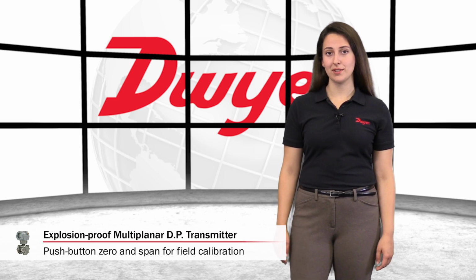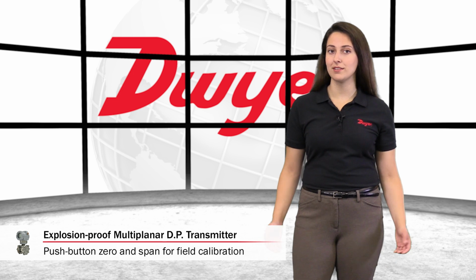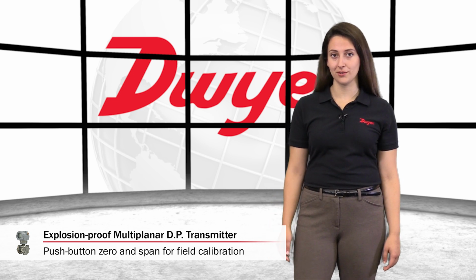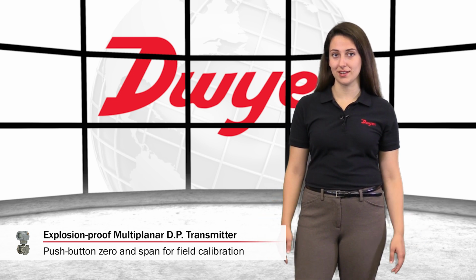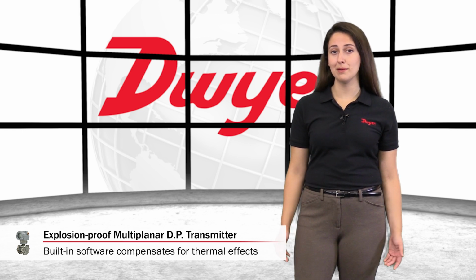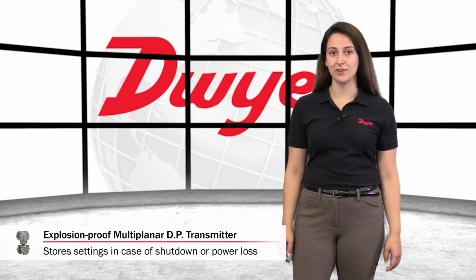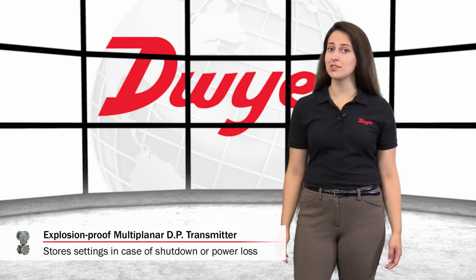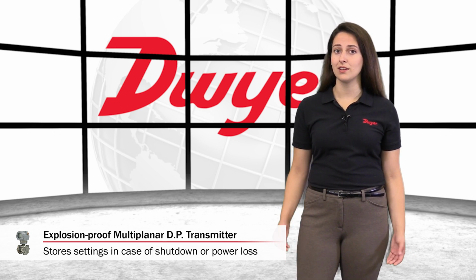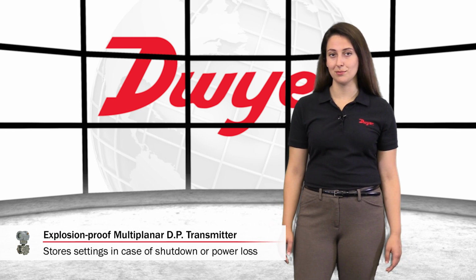The Series 3100 MP features integral push-button zero and span, eliminating the need for a field calibrator for configuration and reducing time necessary to install and maintain. The transmitter's built-in software compensates for thermal effects to improve performance and also integrates a fail mode process function, which stores configuration settings in the event of shutdown or power loss for a faster restart to getting the application back online.